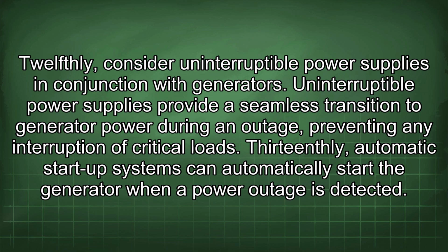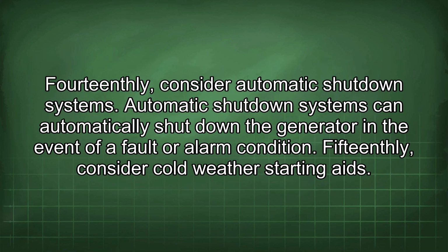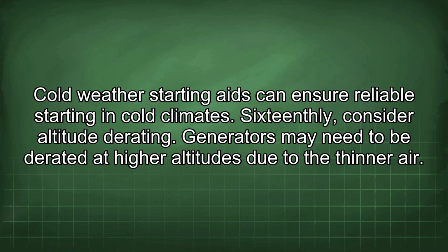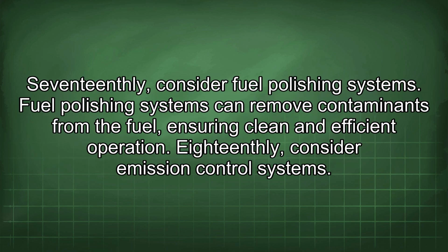13thly, automatic start-up systems can automatically start the generator when a power outage is detected. 14thly, consider automatic shutdown systems. Automatic shutdown systems can automatically shut down the generator in the event of a fault or alarm condition. 15thly, consider cold weather starting aids. Cold weather starting aids can ensure reliable starting in cold climates. 16thly, consider altitude derating. Generators may need to be derated at higher altitudes due to the thinner air. 17thly, consider fuel polishing systems. Fuel polishing systems can remove contaminants from the fuel, ensuring clean and efficient operation.